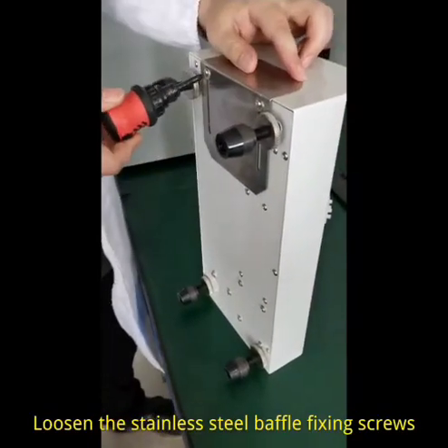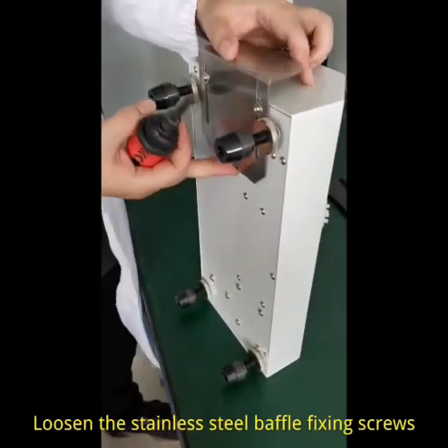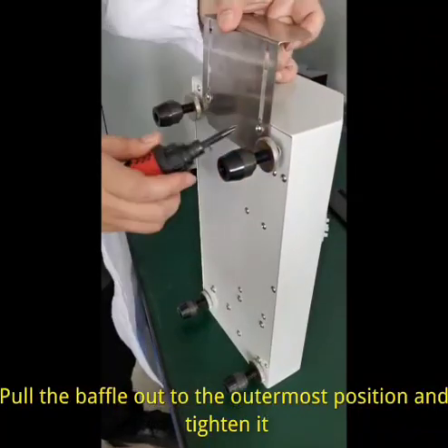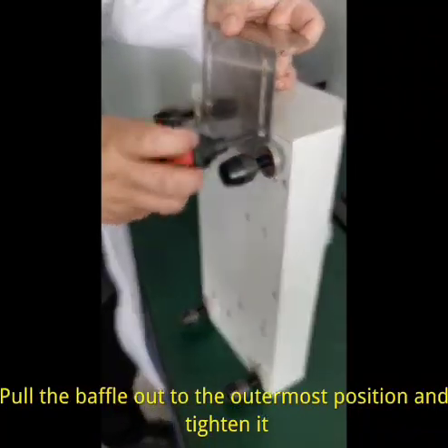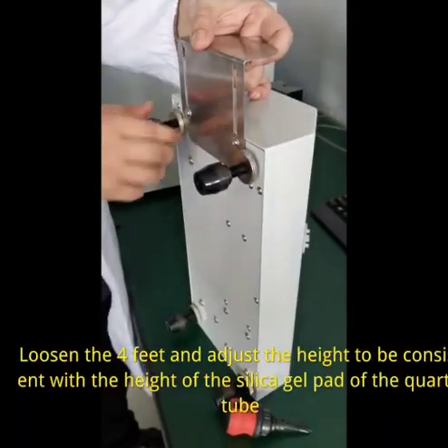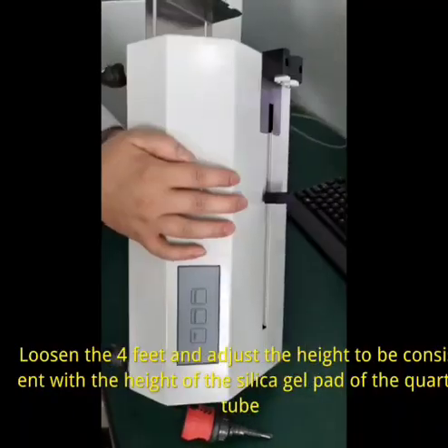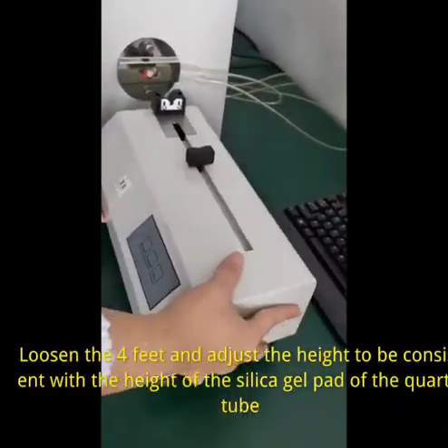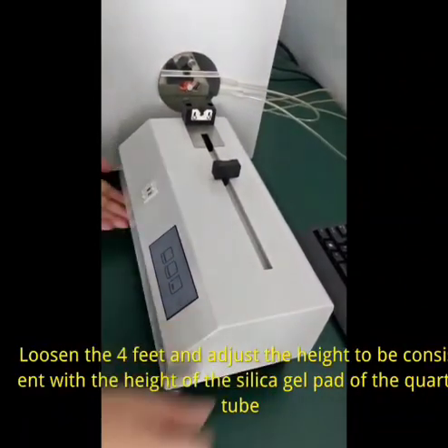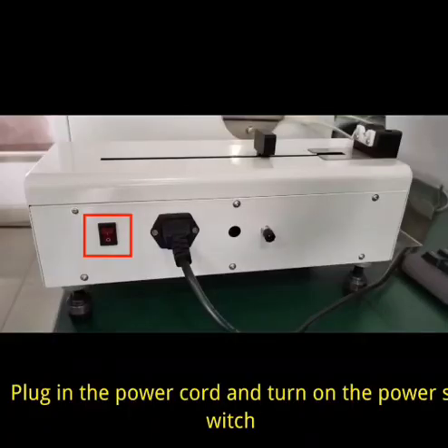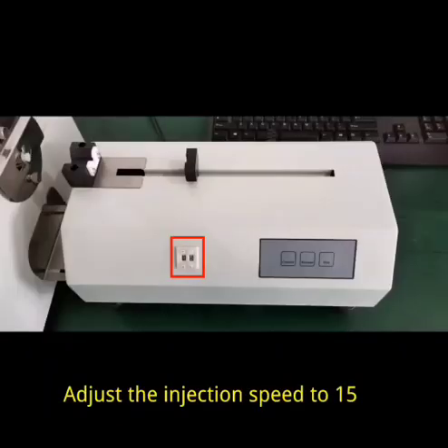Loosen the stainless steel baffle fixing screws. Pull the baffle out to the outermost position and tighten it. Loosen the 4 feet and adjust the height to be consistent with the height of the silica gel pad of the quartz tube. Plug in the power cord and turn on the power switch. Adjust the injection speed to 15.